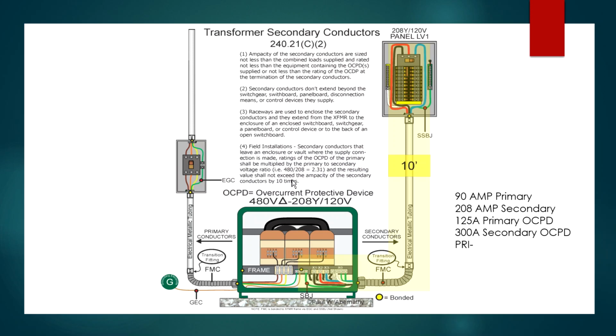Okay, so that resulting value can't exceed the ampacity of the secondary conductors by 10 times. Well, look, no matter what we decided based on our loads, whether this was a 200 amp or a 300, both would comply with this transformer. If you take the value of the conductor that's supplying it, in this case, let's say it was the 2-aught, and it is good for 200 amperes. If I take the 200 times 10, that's 2,000 amps. Well, that 288.75 is no way exceeding the ampacity of these conductors by 10 times. That's not an issue. And in this case, if it was 300 and those conductors are 350 kcmil, then that's 310 amperes times 10, and that is 3,100 amperes. Again, there's no way this value that we calculated is exceeding the ampacity of these secondary conductors by 10 times. So for all intents and purposes, you're not going to run into this.